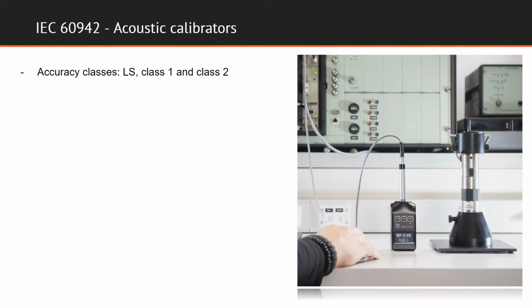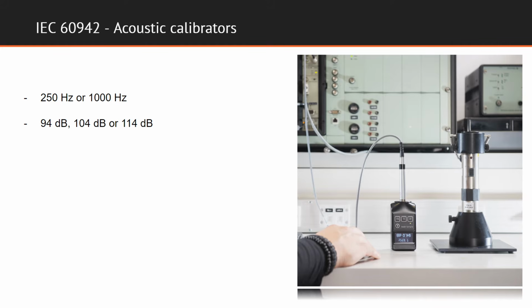The IEC 60942 standard defines three classes of accuracy: LS, Class 1 and Class 2. Class LS is intended for laboratory use only, while Class 1 and 2 are intended for field use. Calibration of the calibrator itself is performed at a single frequency, either 250 or 1000 Hz, and at supported acoustic pressure levels. Usually those levels are either 94, 104 or 114 dB.